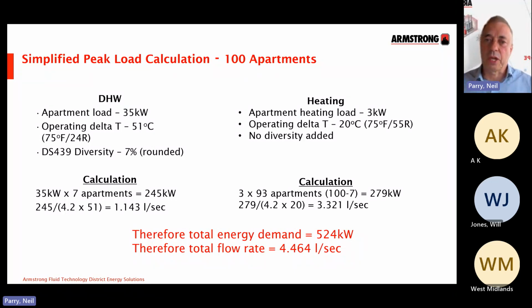So we can see on the left-hand side the domestic hot water calculation, where I'm using an apartment load of 35 kilowatts, an operating delta T from the HIU of 51 degrees in this instance, and then using DS439 as the diversity standard to do the calculation. When you do that calculation, you can see 35 by 7 gives you 245 kilowatts of energy required. And then underneath is that flow rate calculation, where you've got your total energy divided by your constant times the delta T, which gives you 1.14 litres per second.